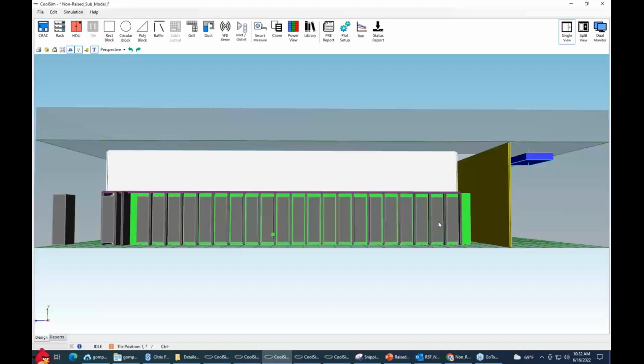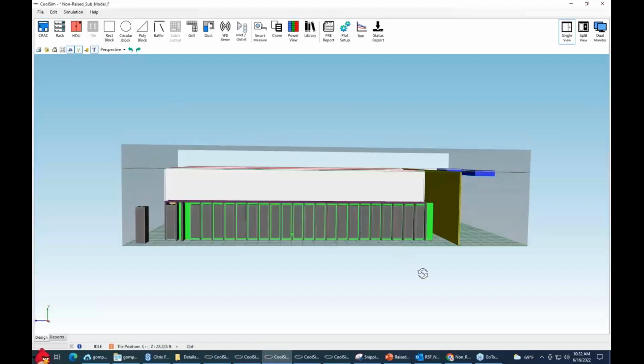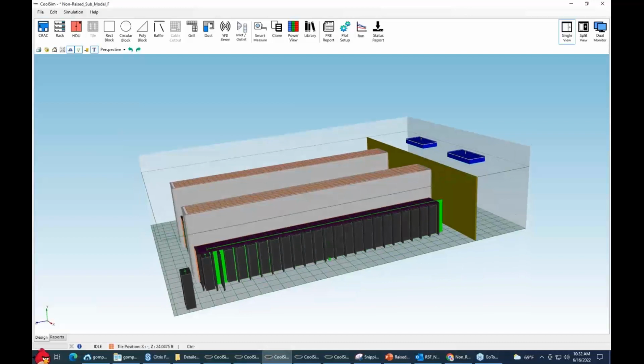It's somebody else's control. So to a large extent, I believe these have been promoted as a lower cost option because you don't have to pay for the raised floor. And because they're, quote, contained, they should, quote, work fine because there are no issues. It's fully contained. You don't need to run CFD on them. This is what I've been told by some. But the more we see them, the more issues we find with them.